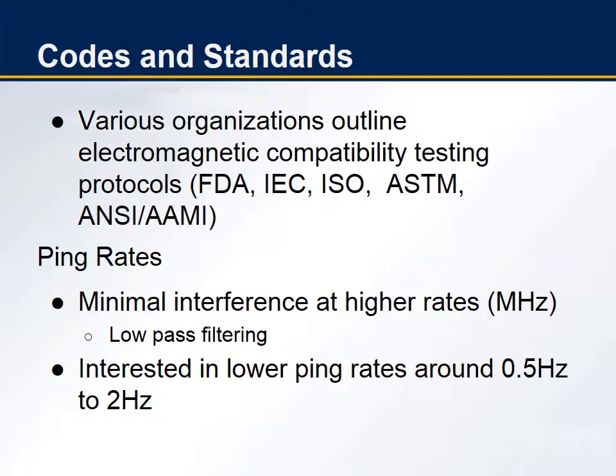One of our challenges was to understand the various electromagnetic compatibility testing protocols. These ensure that proper techniques are used on the device when testing for possible interference. Another challenge was choosing the correct ping rate the RFID would pace to create the most EMI. At high rates, there will be minimal interference due to the pacemaker's low-pass filtering. The pacemaker, however, can't block the lower ping rates produced by the RFID emitter because it's these frequencies that tell the pacemaker if pacing is necessary. And we are interested in the lower ping rates from 0.5 Hz to 2 Hz.